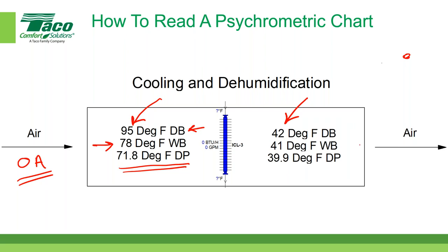Now, one of the weird things that happens in a cooling coil, and this little diagram here represents a cooling coil. Boy, it just didn't want to cooperate today. Cooling coil. There we go. One of the characteristics of a cooling coil is that if you're shooting for, in this case, 42 degrees Fahrenheit, the wet bulb temperature will get fairly close to the dry bulb temperature you're trying to achieve, but for practical purposes it can never get there. That's because some of the air passes through the cooling coil unchanged, and we call that bypass air. Any coil, no matter how many rows you have in it, has a certain number of molecules of air that slip through unaffected. So in most practical applications, we can never get the wet bulb temperature to equal the dry bulb off of a cooling coil.